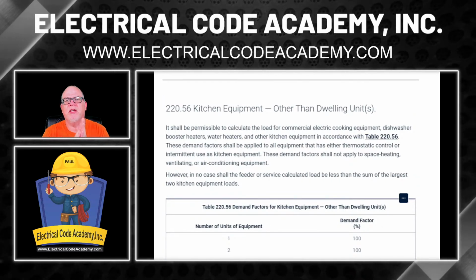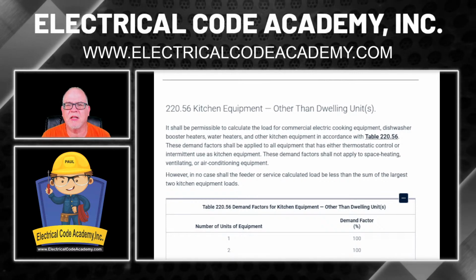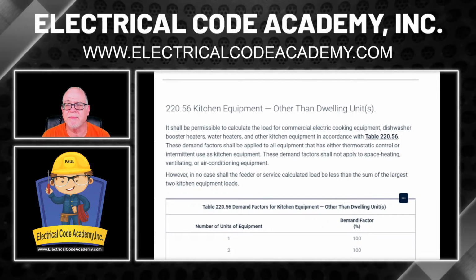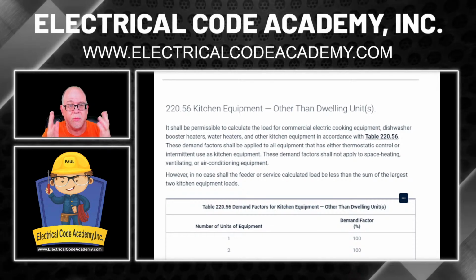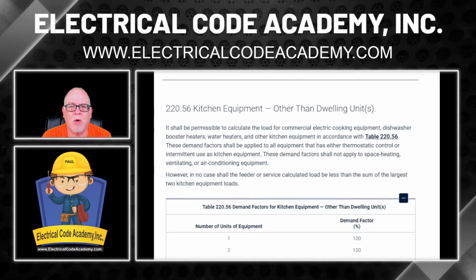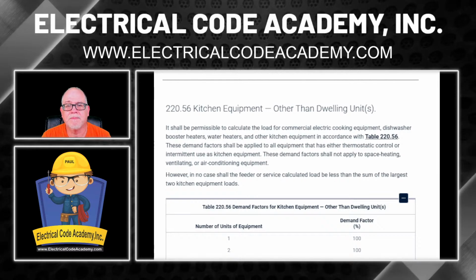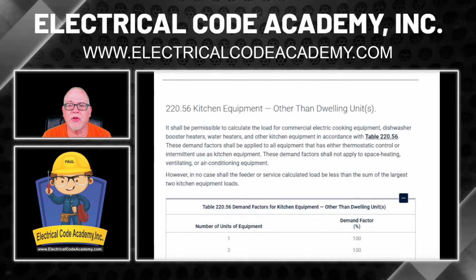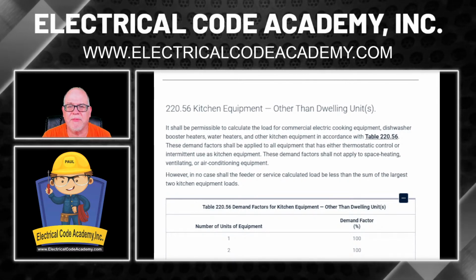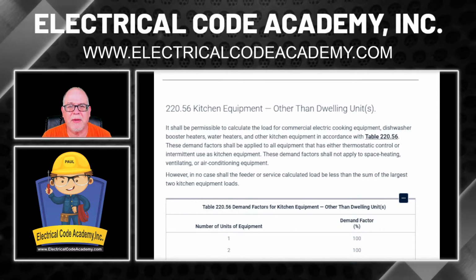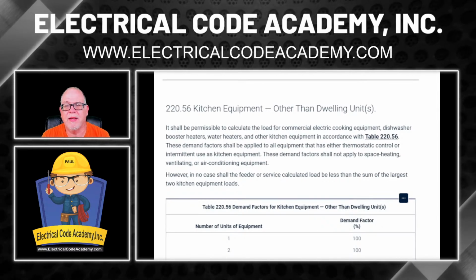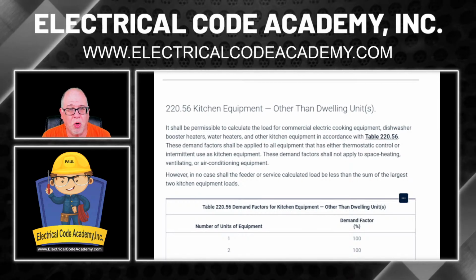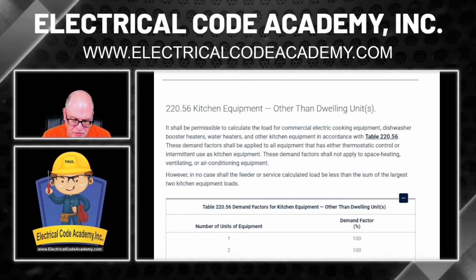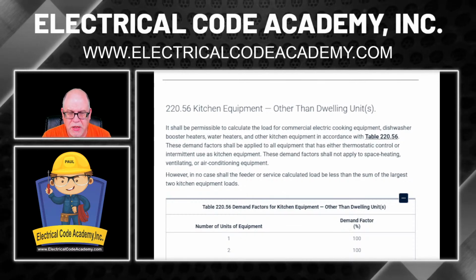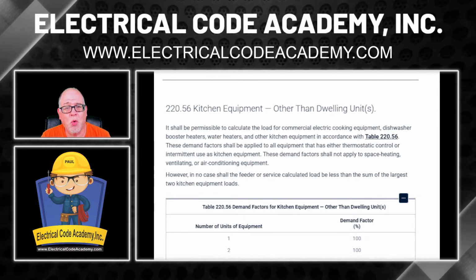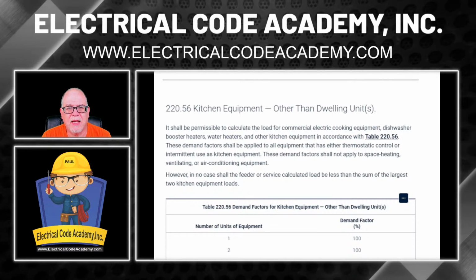So let's read it. It says, it shall be permissible to calculate the load for commercial electric cooking equipment. Okay, so we do have cooking. We have ovens, so we're good there. Dishwasher booster heaters. We do have a booster heater. Water heaters and other kitchen equipment in accordance with table 220.56. It also says these demand factors shall be applied to all equipment that has either thermostatic control, and most of this stuff, the ovens, the grills, the deep fryers, and all that kind of stuff, are going to be thermostatic controlled. It says, or intermittent use as kitchen equipment.